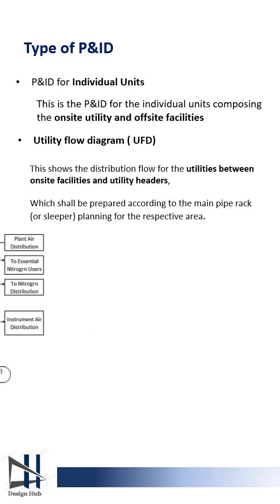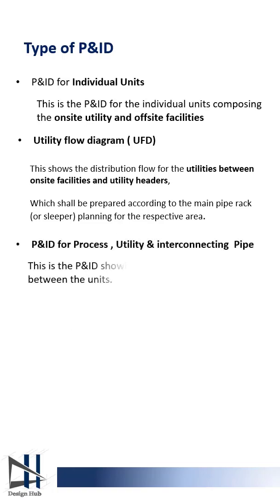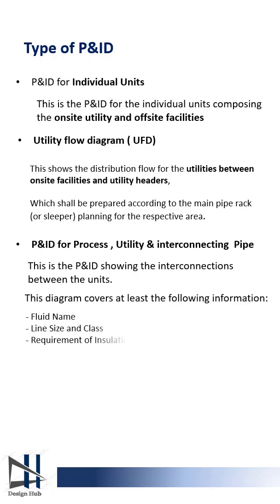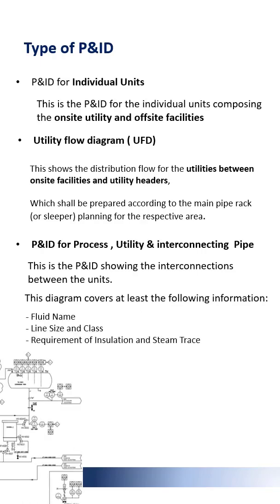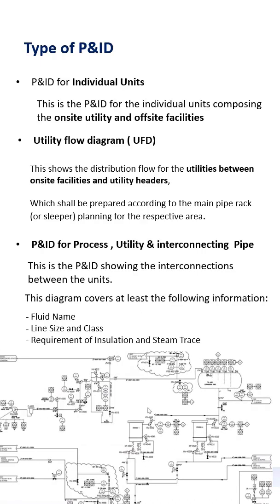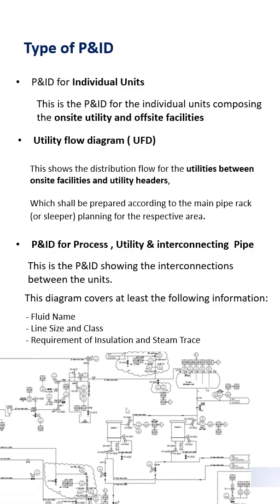The third kind of P&ID is the main P&ID, which connects all the units and utility interconnections. This kind of P&ID includes information such as fluid name, line size, flange class, and requirements for insulation or tracing.